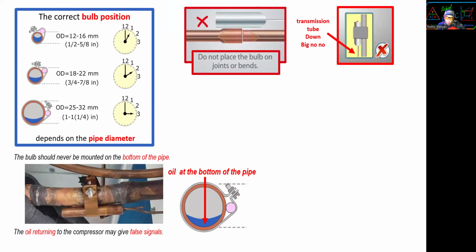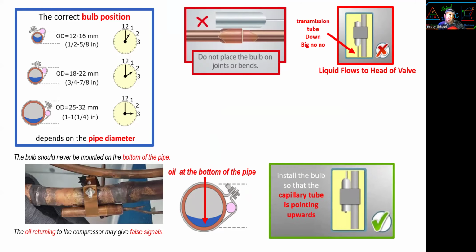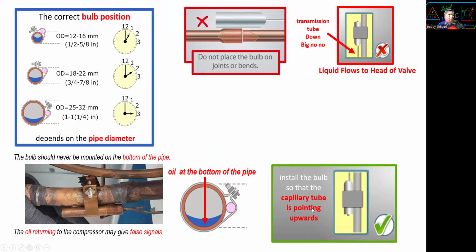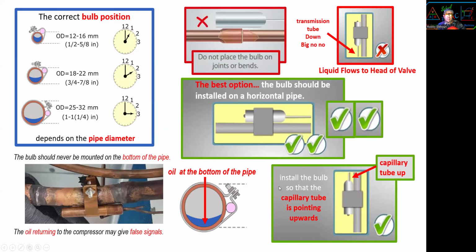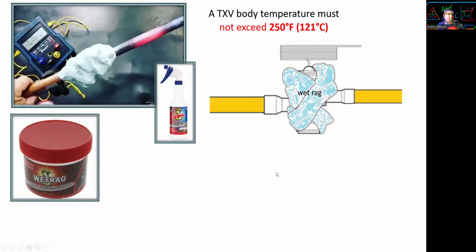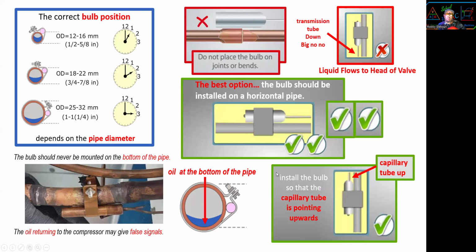The transmission tube should never go down, because if it goes down, the liquid will go to the head of the diaphragm, and the diaphragm will not work properly. The cap tube should be pointed upward, so the transmission line. The best option is this way, but sometimes you don't have a chance. Sometimes, especially on walk-in coolers, you don't have room to put it.